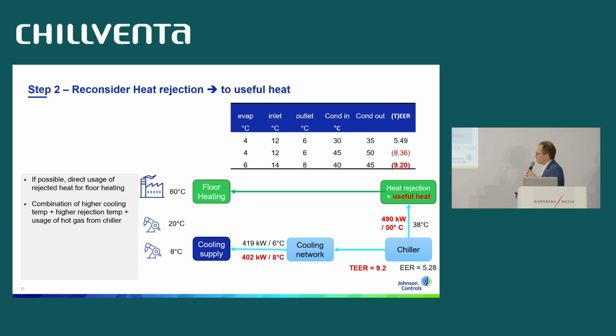And in addition, we have a combination of higher cooling temperatures, so 2 Kelvin on the cooling network, higher rejection temperatures, and usage of the hot gas from the chiller to even overcome 50 degrees Celsius to achieve 60 degrees floor heating. So you have a double usage. You have cooling demand on the cooling network, and you can easily manage a floor heating of your industrial process. And this gives you a TEER. This is the number again of 9.2. For the same amount of electricity, you get heat and cool.